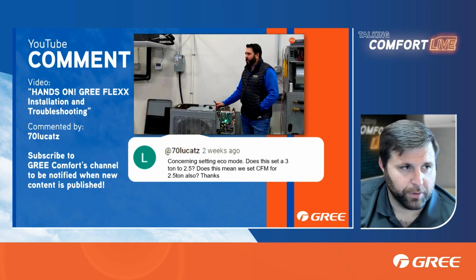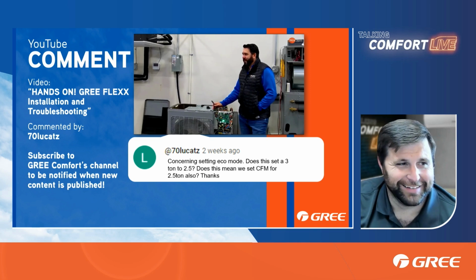I think you could set it for 2.5 tons worth of airflow because it's going to be running economy mode on the outdoor unit. But even if you kept it at the 3 ton of operation as far as airflow, I still think you're talking about a minimal difference in operation. It actually gives instructions in the service manual or installation manual about how to set those and use the eco mode and the strong mode to give that 0.5 ton difference.